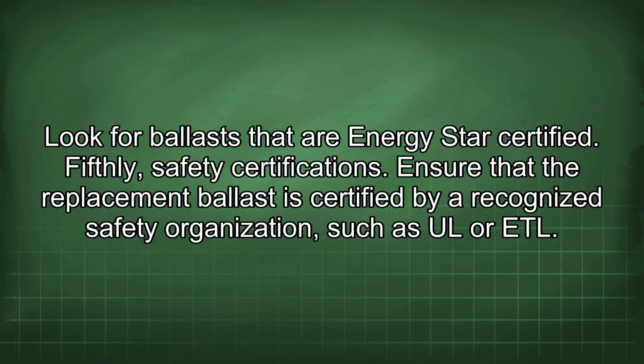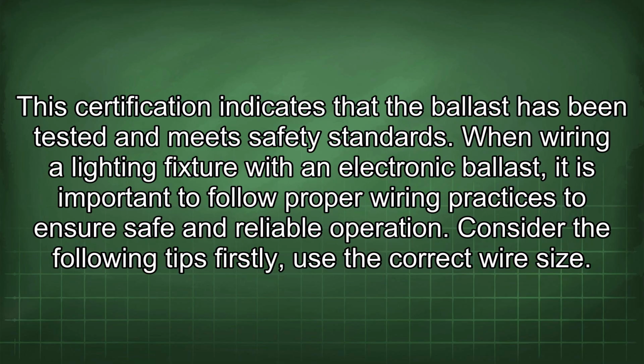Fifthly, safety certifications. Ensure that the replacement ballast is certified by a recognized safety organization such as UL or ETL. This certification indicates that the ballast has been tested and meets safety standards. When wiring a lighting fixture with an electronic ballast, it is important to follow proper wiring practices to ensure safe and reliable operation. Consider the following tips.